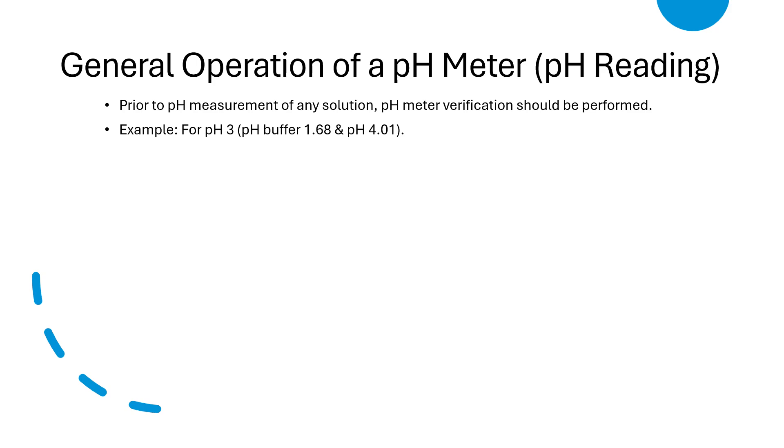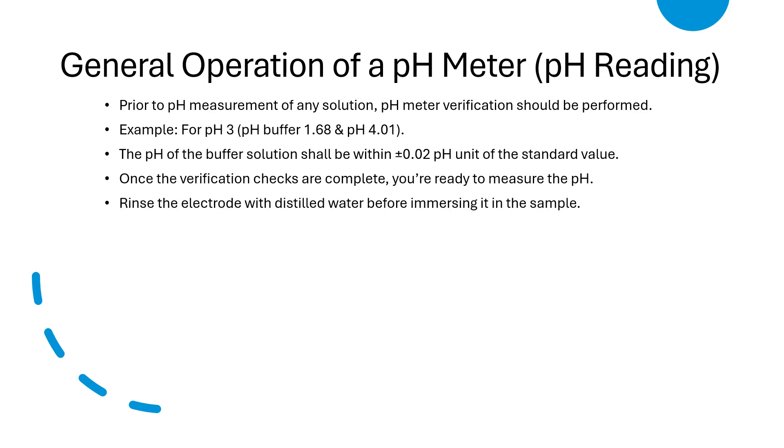The pH of the buffer solution shall be within plus or minus 0.02 pH units of the standard value. The stabilized value reading should be within plus or minus 0.02. Once the verification checks are complete, you are ready to measure the pH. Then rinse the electrode with distilled water before immersing it into the sample.